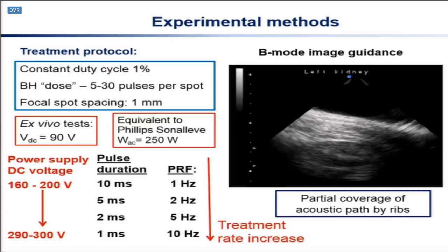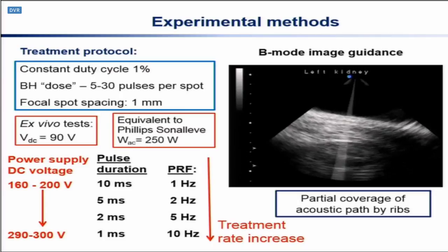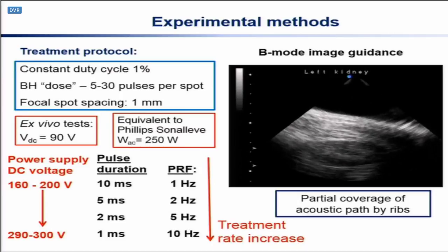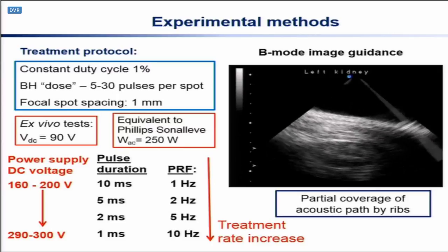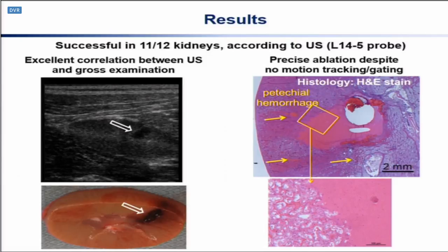During the treatment, you can see this white echogenic spot that shows the treatment size and is caused by the bubbles induced by boiling histotripsy. And after sonications, this spot will be hyperechogenic due to the loss of tissue structure. So here is the result of one case after the treatment. You can see the photo of the lesion on the gross picture below, and the ultrasound image is on the top. And the size and the position of the lesion correlate very well between these two images.